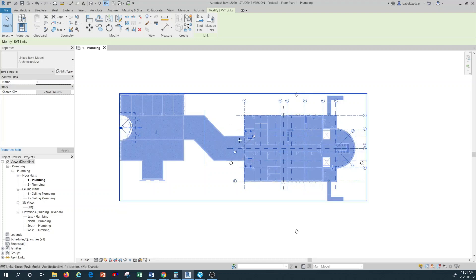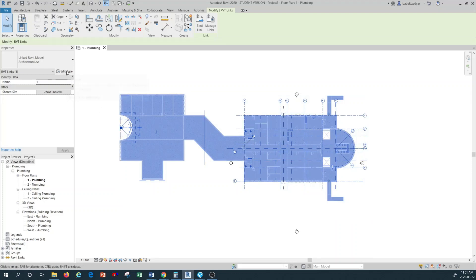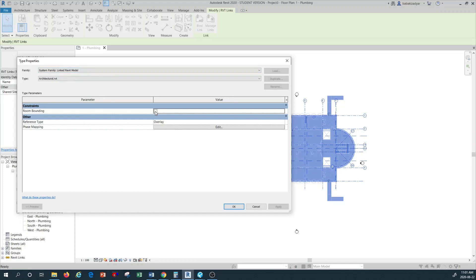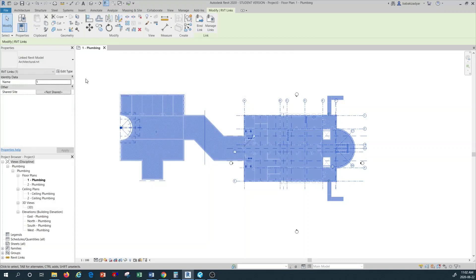Once you do that, make sure you enable the room boundaries by going to Edit Type for the linked architectural plan. Under Room Bounding, make sure that it is checked. This ensures that Revit understands the boundary of the room walls and doors, so that when you create spaces you can create individual spaces allocated to every room. Then click Apply and OK.